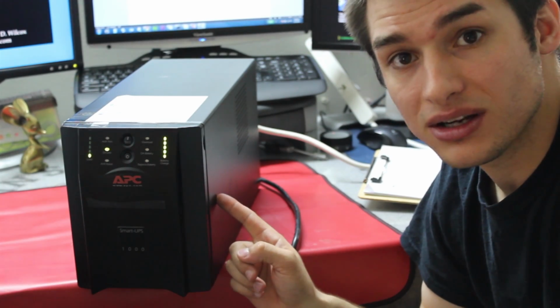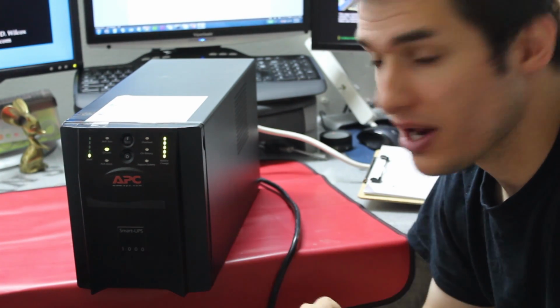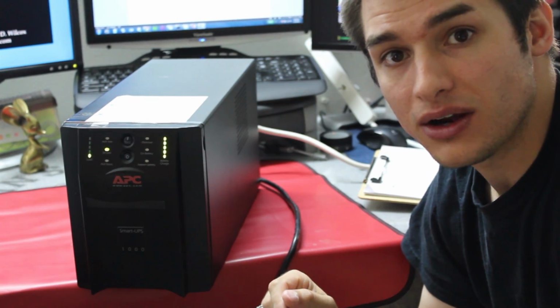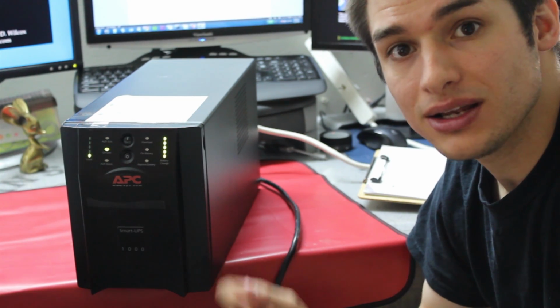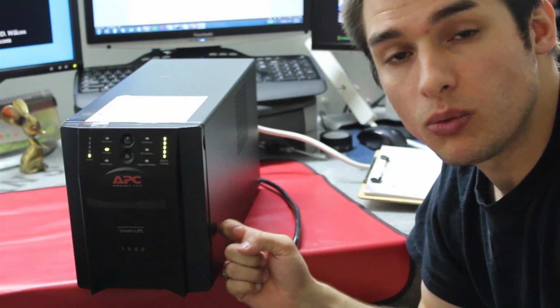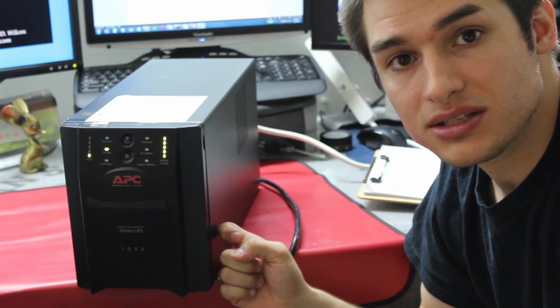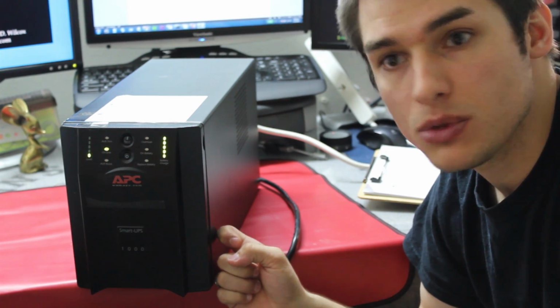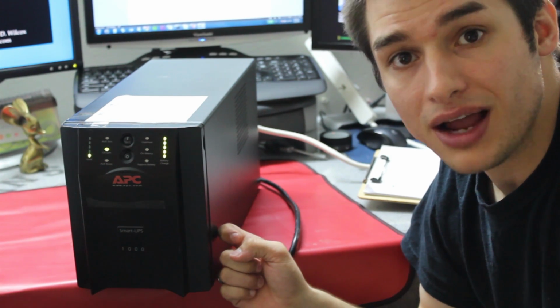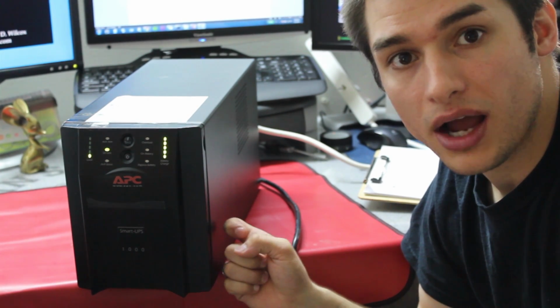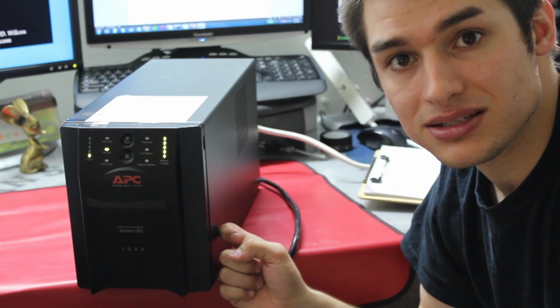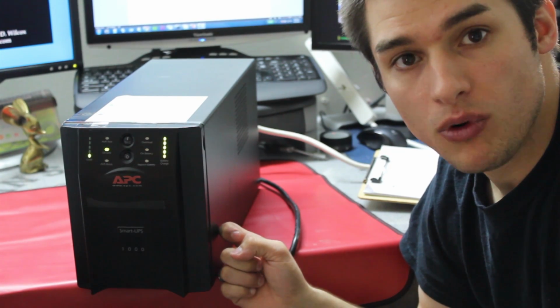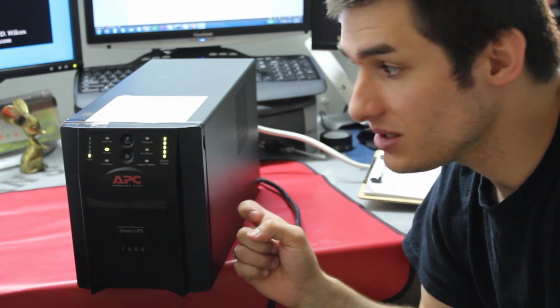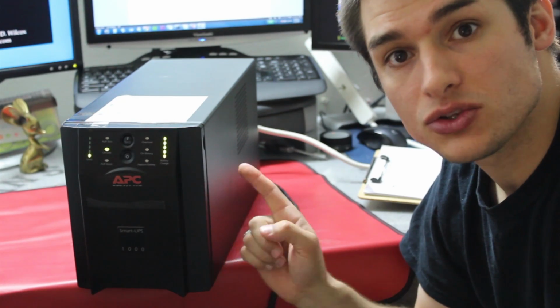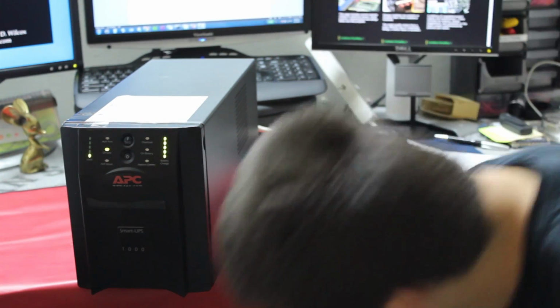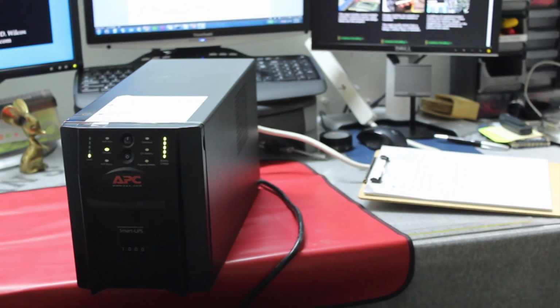How do you know that this thing's going to work? Even though it says battery good here, the indicator lights are saying excellent, way to go, you're protected. How do you know? Well, one of the things that I've always done when installing systems like this, whether it's for a server room or for a client, is I unplug it. While everything is on, I unplug it. This is how we're going to test how well these perform. This is what it's designed to do. And we're going to unplug it while this thing is on. So let's go ahead and do that right now. Let me just unplug it here.